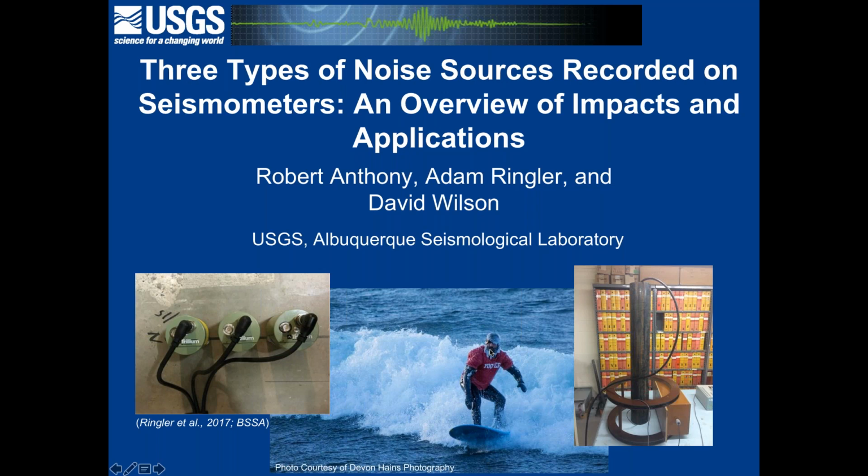But as I was going through my PhD, I don't think I fully appreciated that seismometers record many noise signals that aren't related at all to ground motion. And one of those is the self-noise of the instruments themselves. This is usually how we test them, by co-locating 3 instruments together in a quiet place. And that almost bit me on my last paper in my PhD, so I'll show that example.